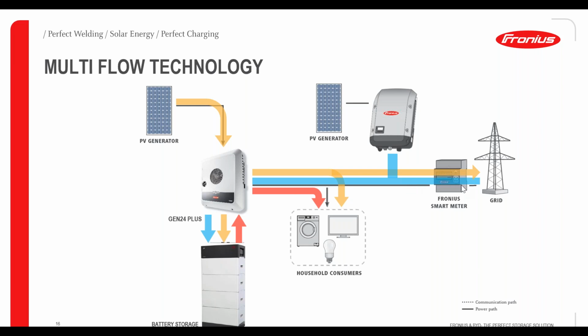There is no direct communication between the smart meter and the Symo inverter here, but as soon as there is a surplus energy coming from the normal Symo going to the grid, then the smart meter knows it is the surplus energy. Then it starts communication with the hybrid inverter, and the hybrid stores that energy in the battery instead. In this case, you can even remove PV from the DC side, and you can connect them to the second inverter on the AC side, so you still continue producing.